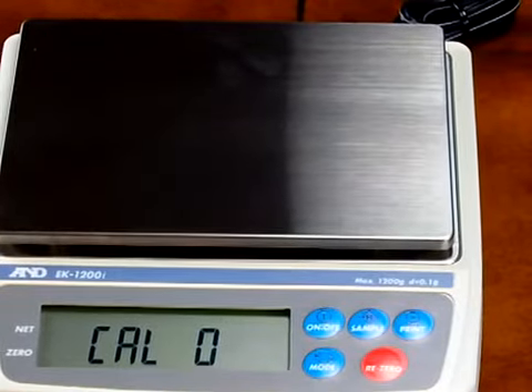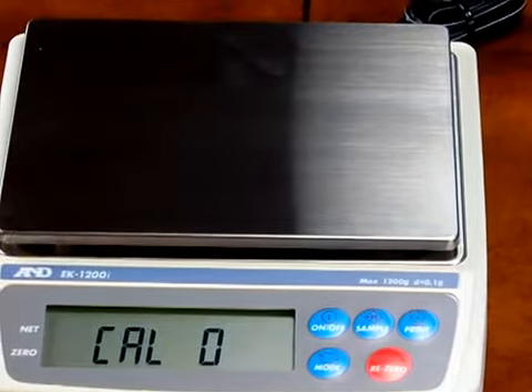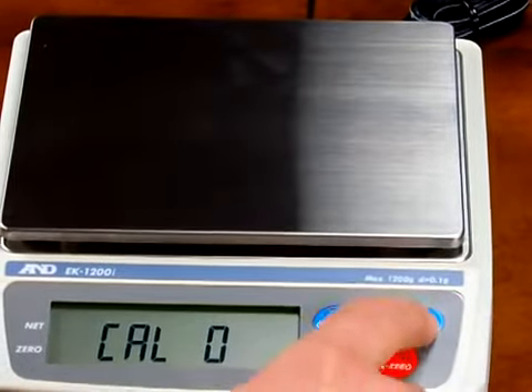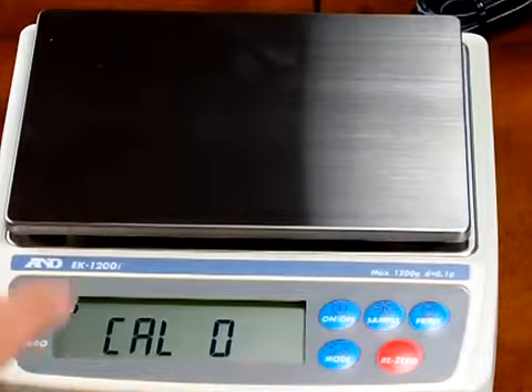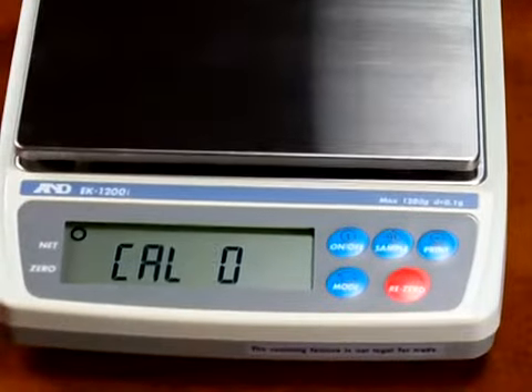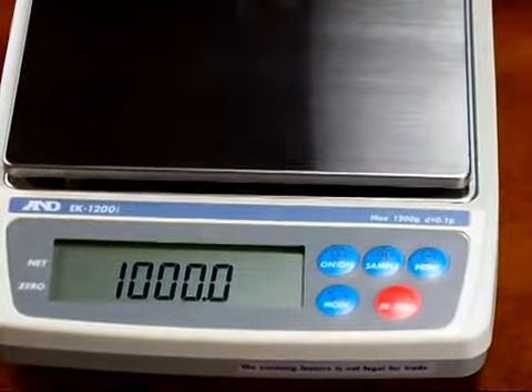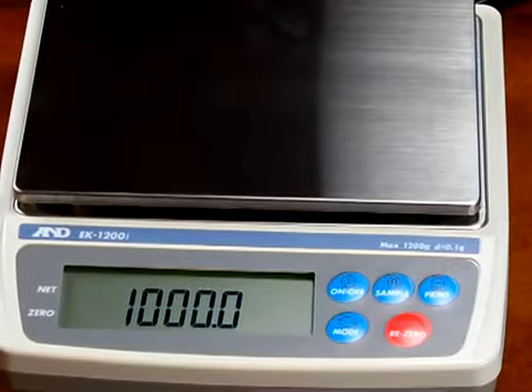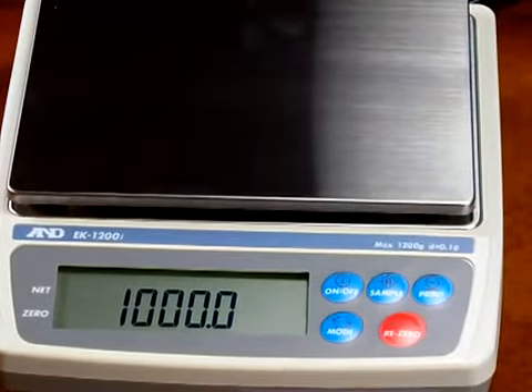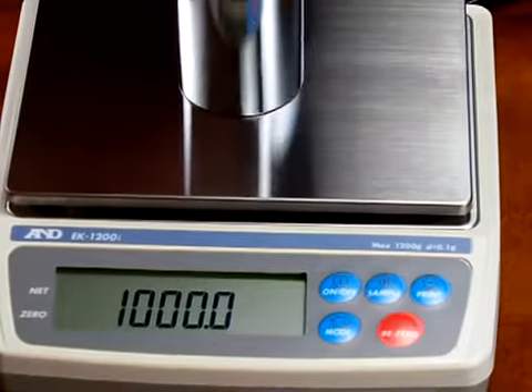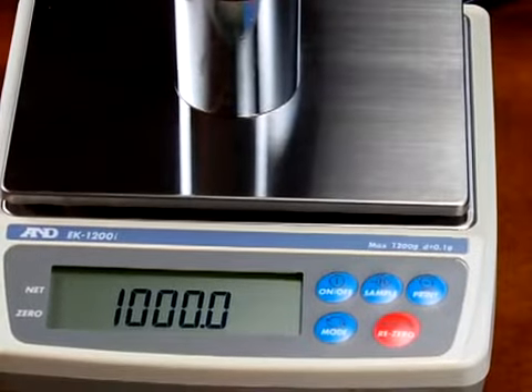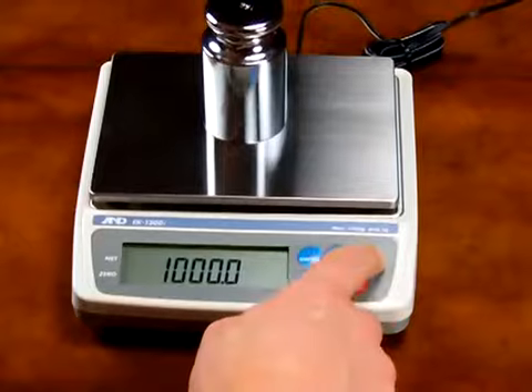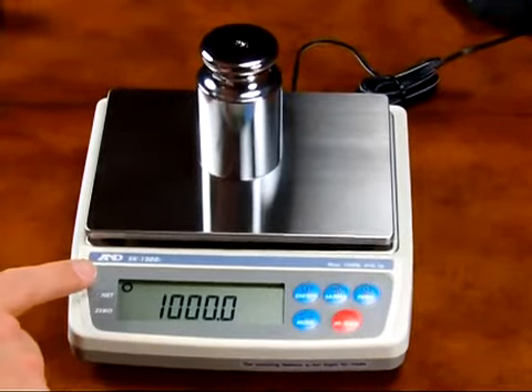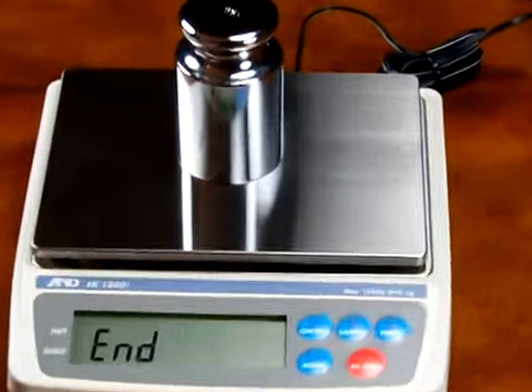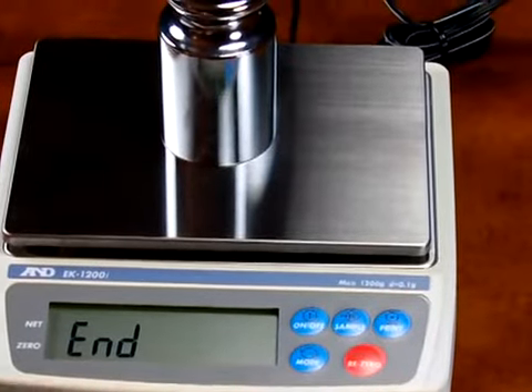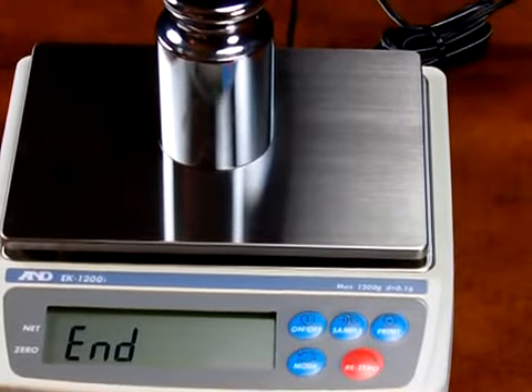So now to start the calibration, all we have to do is press the print key, and we're now calibrating the balance with nothing on the platform, and that is storing the 0 reference point, and now it's showing 1000 grams. So we place our 1000 gram calibration mass on the scale, and we'll press the print key again. And notice when we press it, the circle in the top, that's confirming that it stored the value, and now it says end.